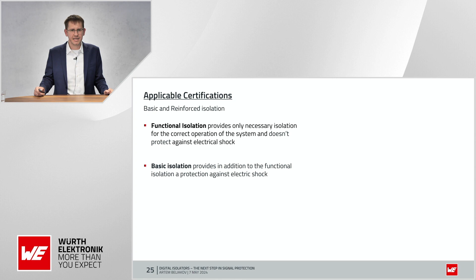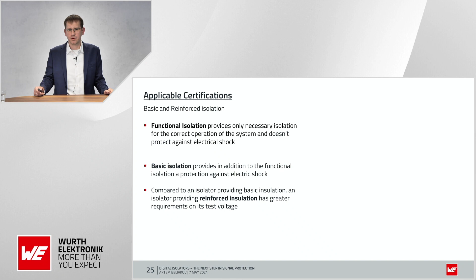As you know, on the market exist a few types of isolation level. The main ones are functional, basic, and reinforced isolation. Functional isolation provides only the necessary isolation for the correct operation of the system and doesn't protect against electric shock. Basic isolation provides, in addition to the functional isolation, protection against electric shock. And compared to an isolator providing basic isolation, an isolator providing reinforced isolation has greater requirements on its test voltage. But what do greater requirements mean? You can see on this table.